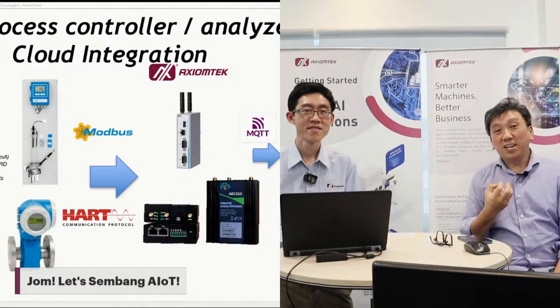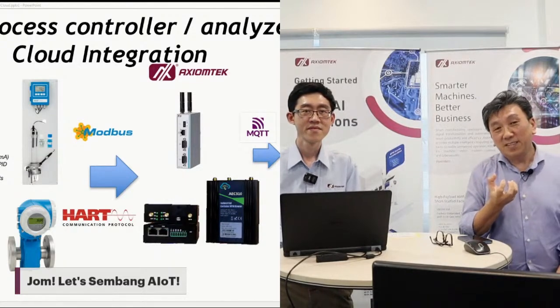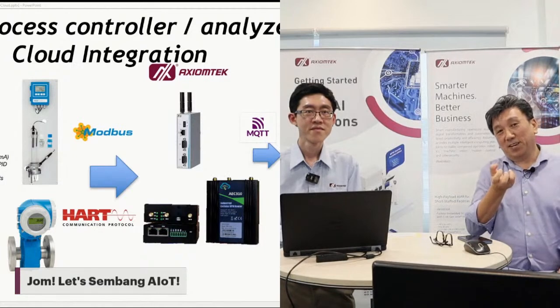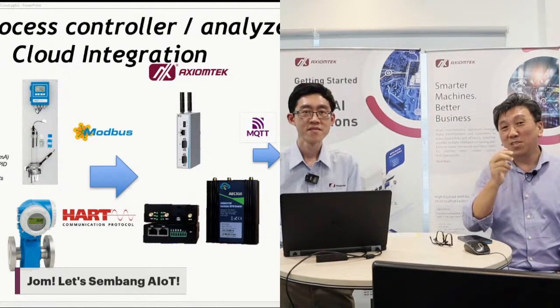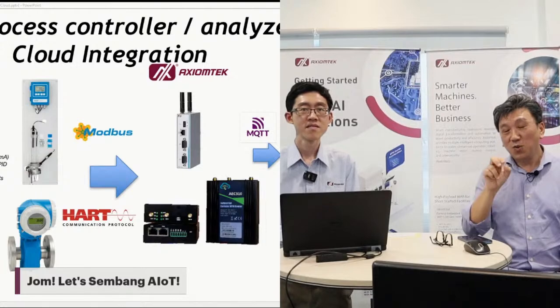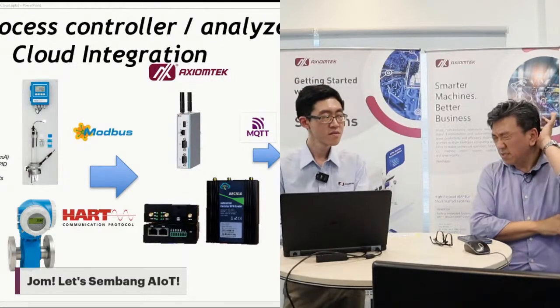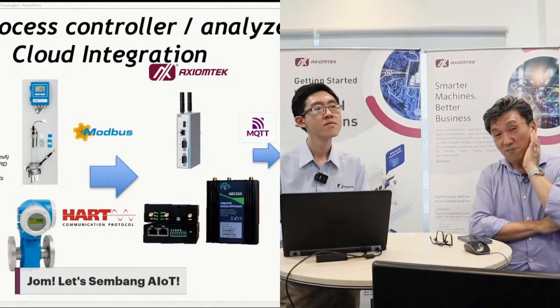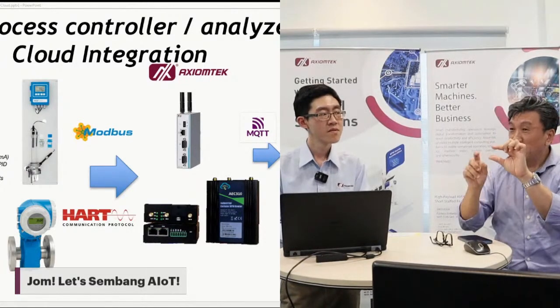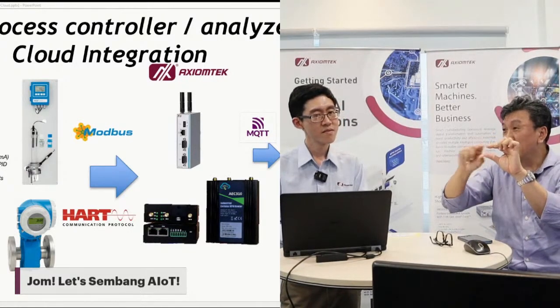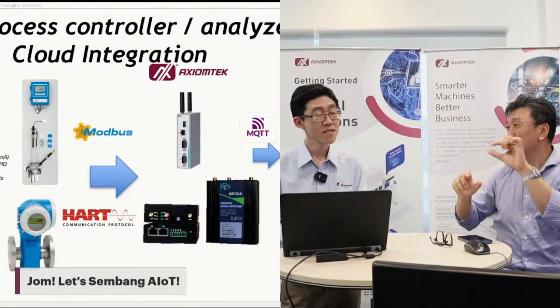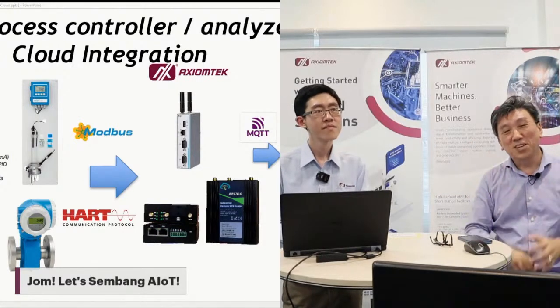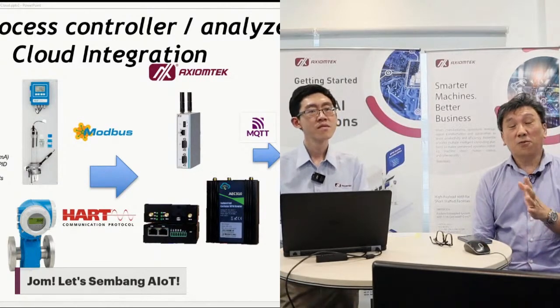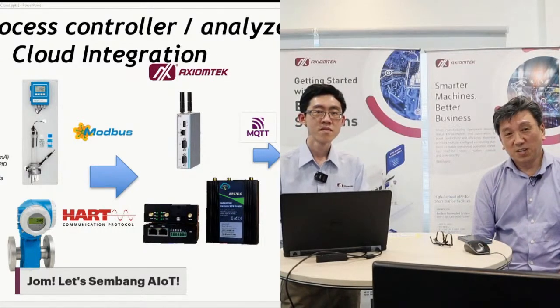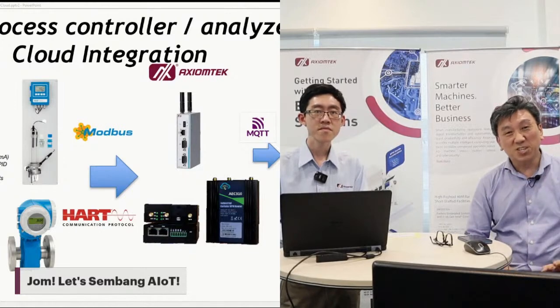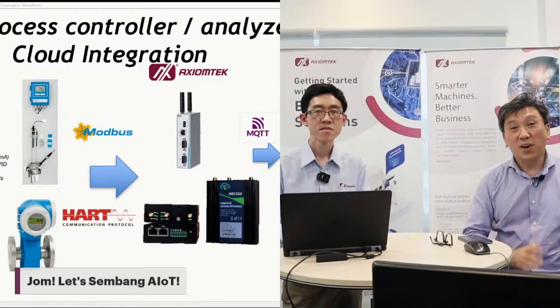But at the other end, you have this listener or HART transceiver that talks to the equipment through the same bus. This part is very, very interesting. I think it's a very wonderful invention. On the DC, you can still superimpose some data communication within the 4 to 20 milliamp bus. This is very good. I think until now, if you go to those, especially waterworks instrumentation, all those things, HART is still very, very relevant.